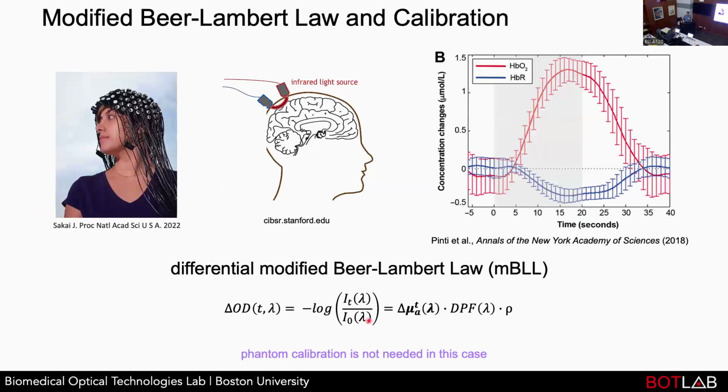Do you assume homogeneity of titanium dioxide when the silicone cures? I'm assuming some of it falls down. What people have done is take these phantoms and cut them in half, so you can see the cross section and look to see if optical properties change through the thickness of the phantom. I think mostly we're confident that they're homogeneous, but not fully confident. It's a little hard to publish on, and we'd love industry to solve this problem for us.